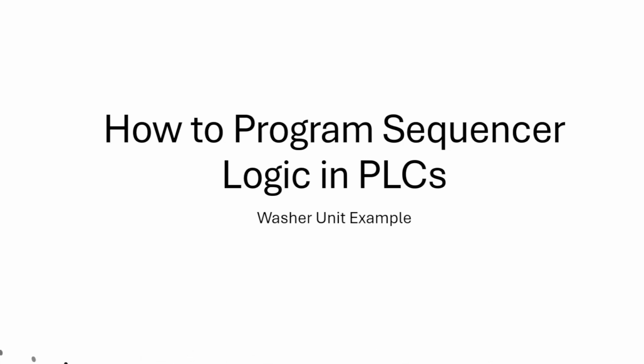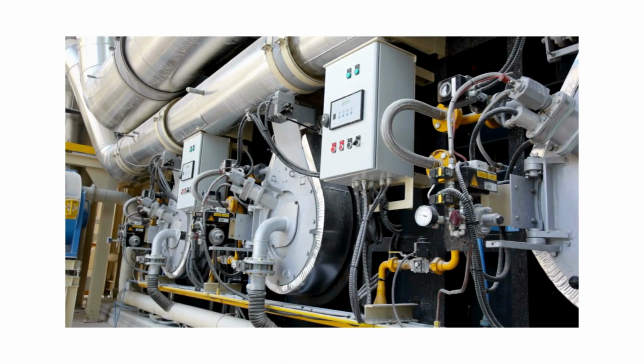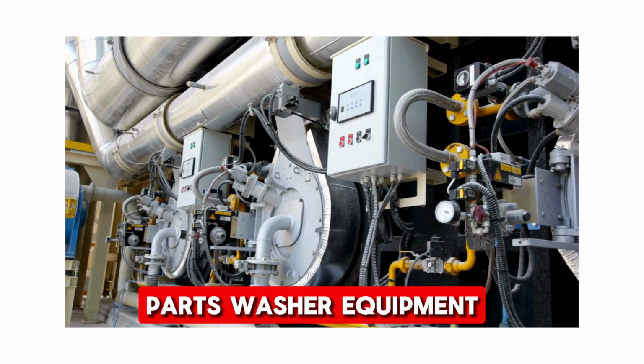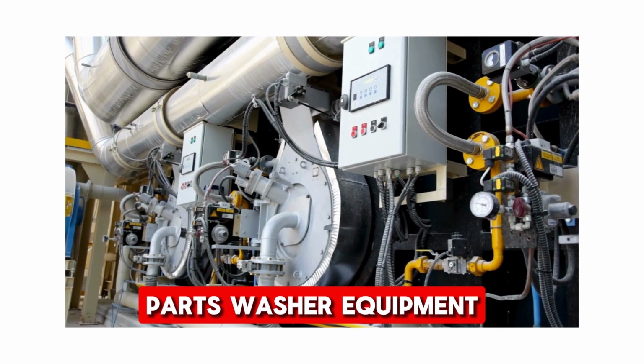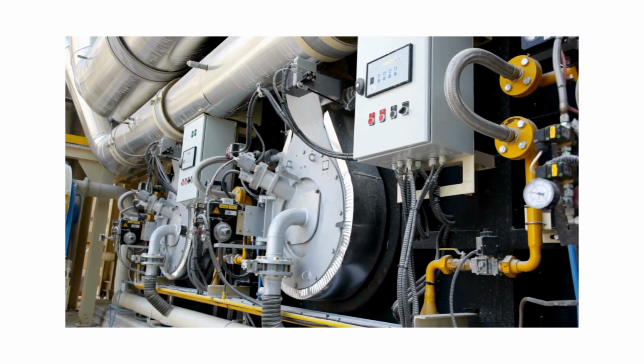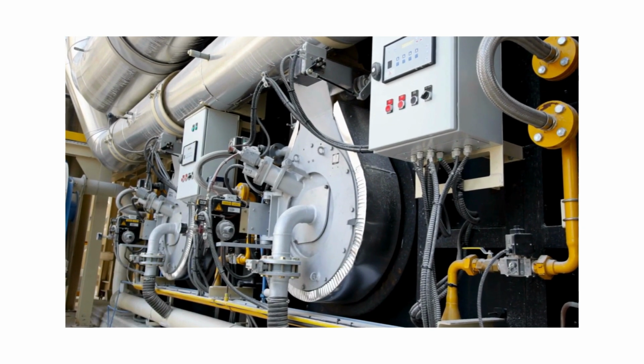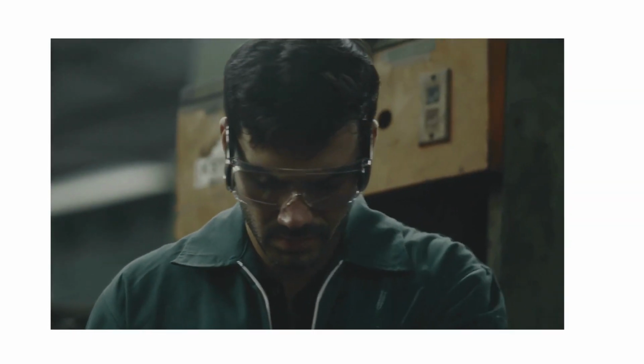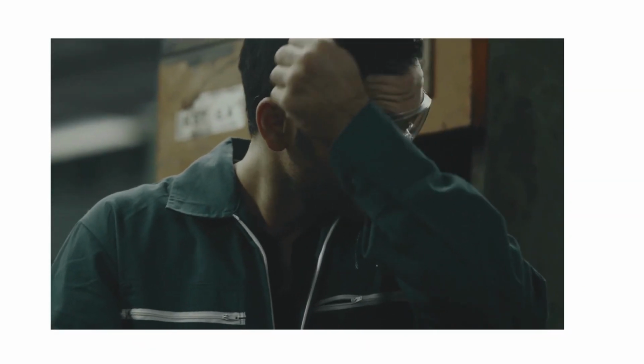I was once troubleshooting a washer tank system. It was supposed to fill it with water, heat the water, and then spray, but the logic was messy. The machine started spraying before the tank was even full. Operators were frustrated. Nothing made sense. So I stopped and rewrote the logic using a clean sequencer structure, and it worked flawlessly.